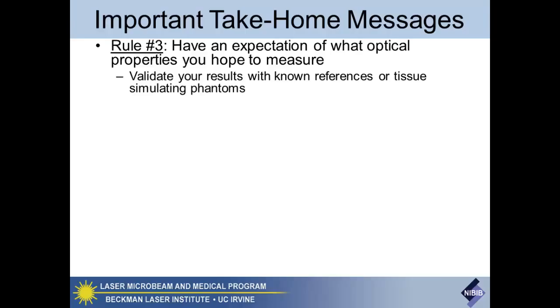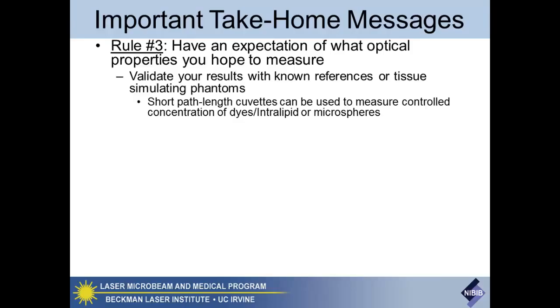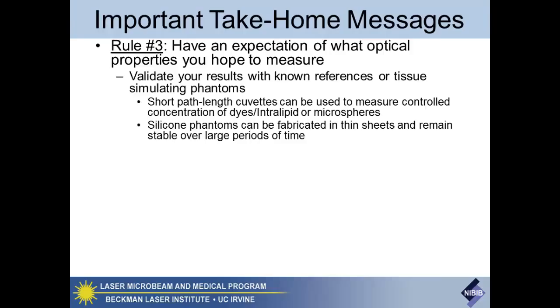Third rule — and probably should be the first rule — is to have an expectation of the optical properties you want to measure. What we can't control are the inefficiencies of actual physical measurements, but we do have an exact solution, so we have some way of anticipating what we will expect to encounter. If you know exactly what the optical properties are, or have some idea of the range you intend to measure, you can anticipate what you'll encounter when you make physical measurements. You can use other references that approximate that, that you actually know in advance, to calibrate your system as a sanity check. Using short path length cuvettes with controlled concentrations of dyes, or controlled concentrations of microspheres where you can model using Mie theory what the scattering properties should be in advance, will give you some way of validating your unknown sample to make sure it fits within a range. Using silicone phantoms — which you can make, fix, and measure again and again over time — is another approach.